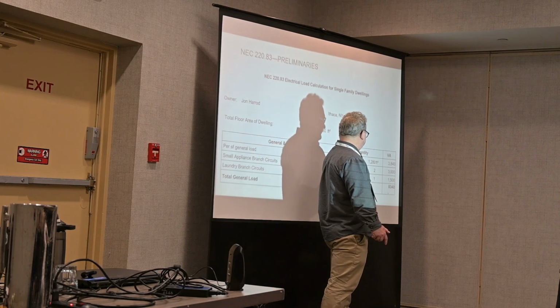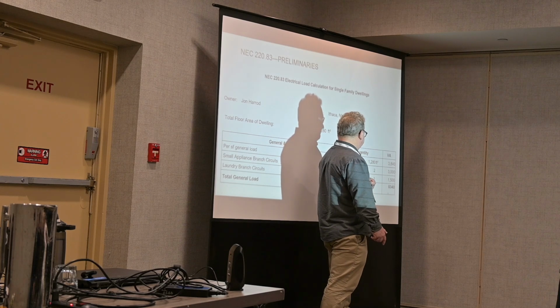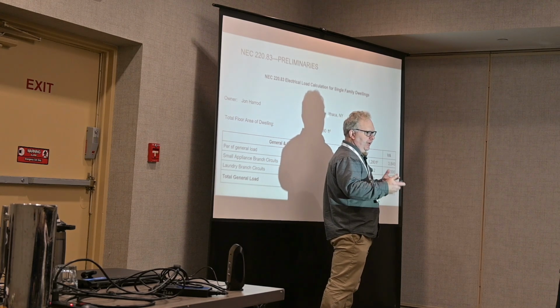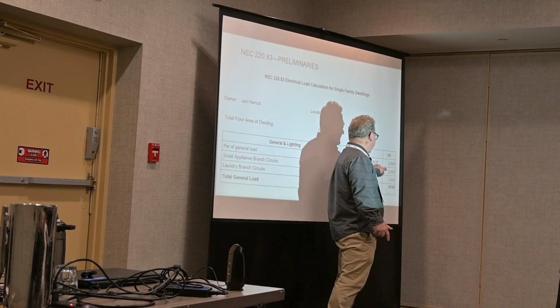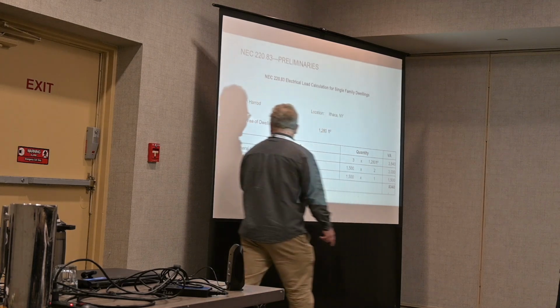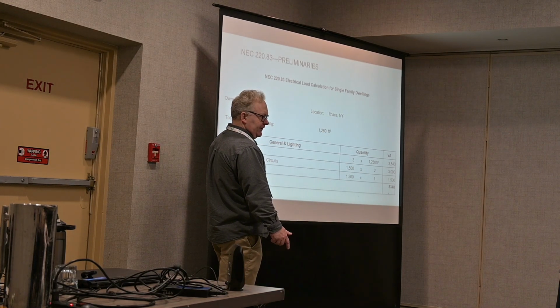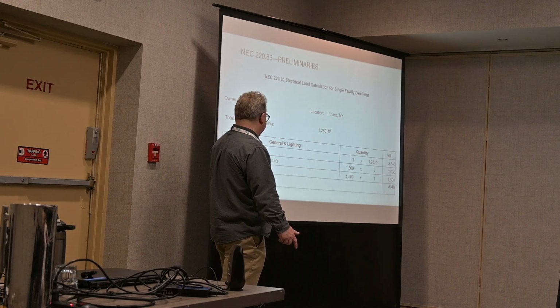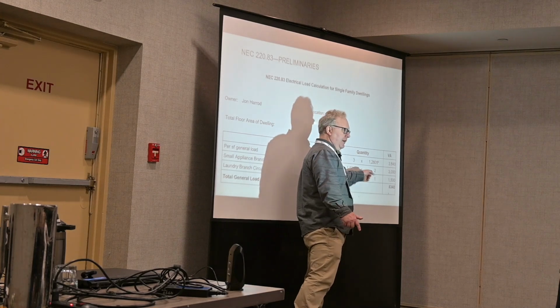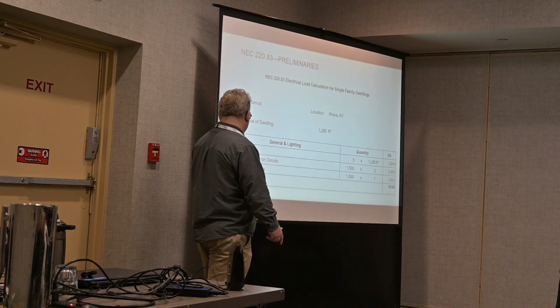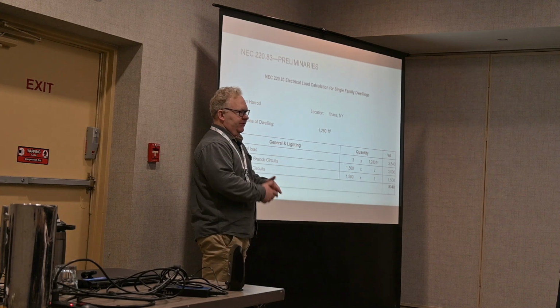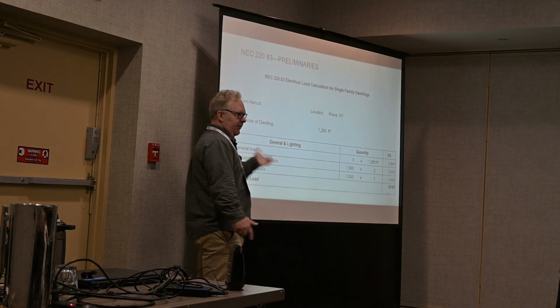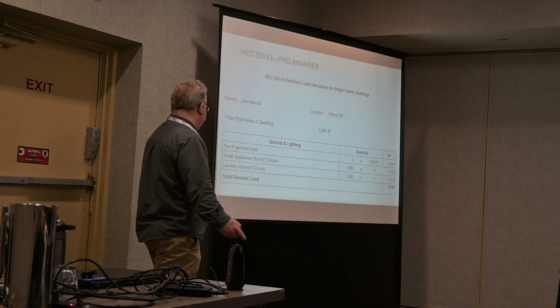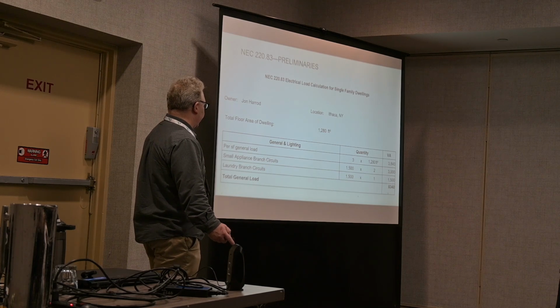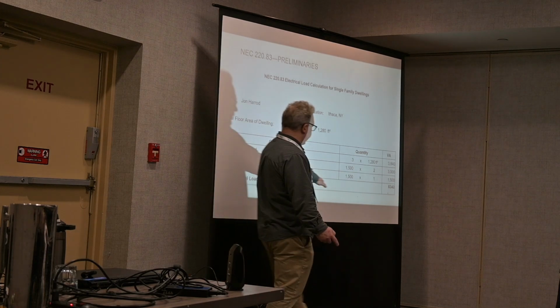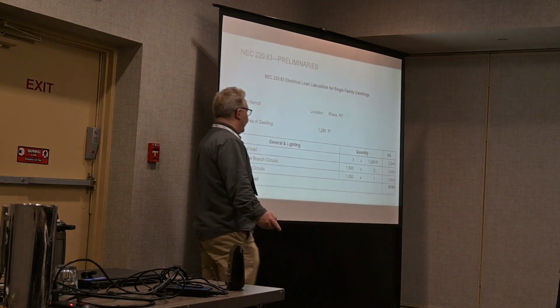We need to put in 3 VA per square foot of conditioned space. And that's to account for lights, plug loads, things like that. So I need to know the square footage of the conditioned space times 3. Small appliance branch circuits, these are my 20 amp countertop circuits. I've got 2 of those. The calculation requires you to put in a minimum of 2. And then your laundry branch circuits. This is, again, a 20 amp single pole circuit that powers your washing machine. And if you have a gas dryer, it can also plug into that. So that's our general load. In my case, 8340 VA.